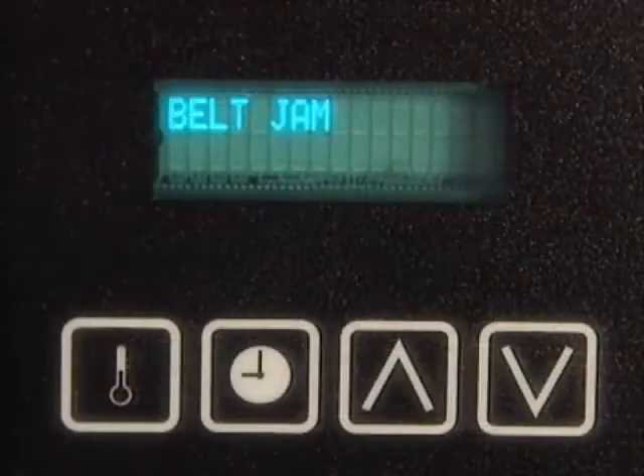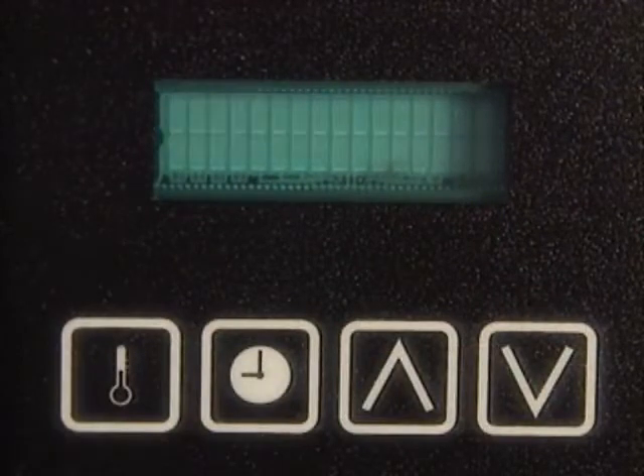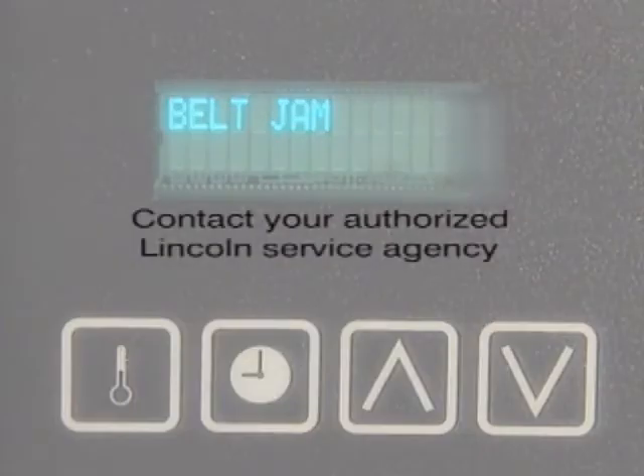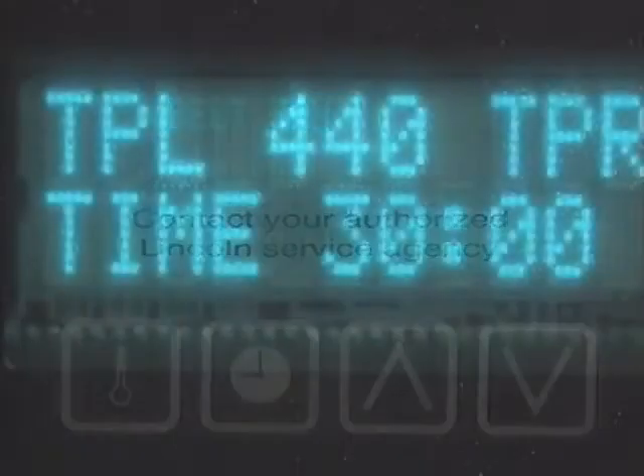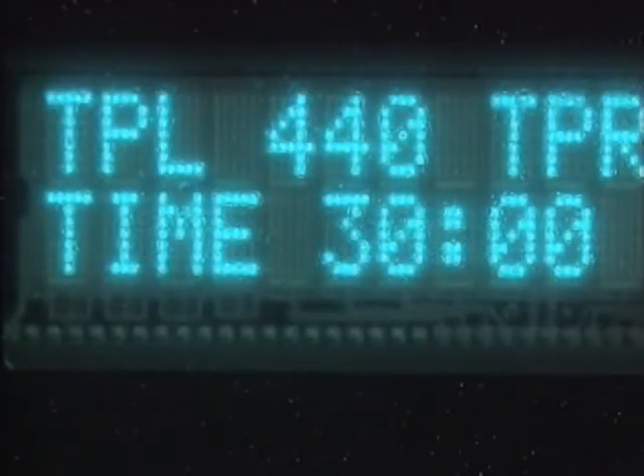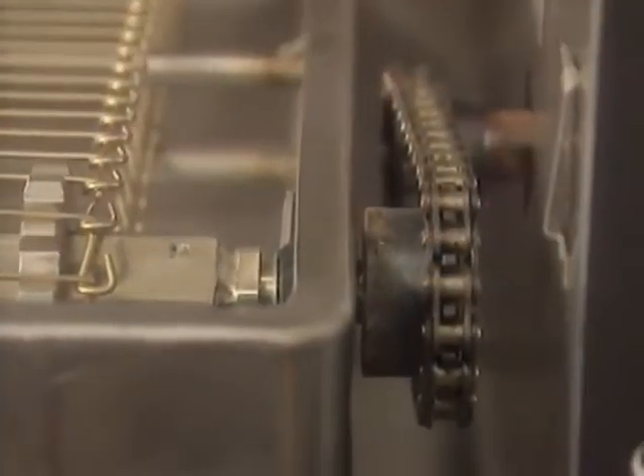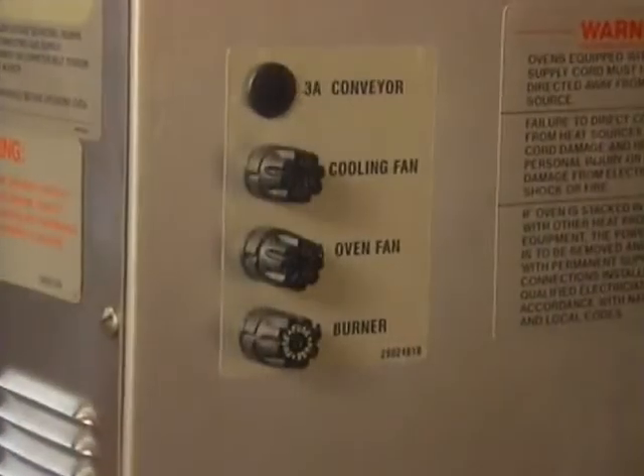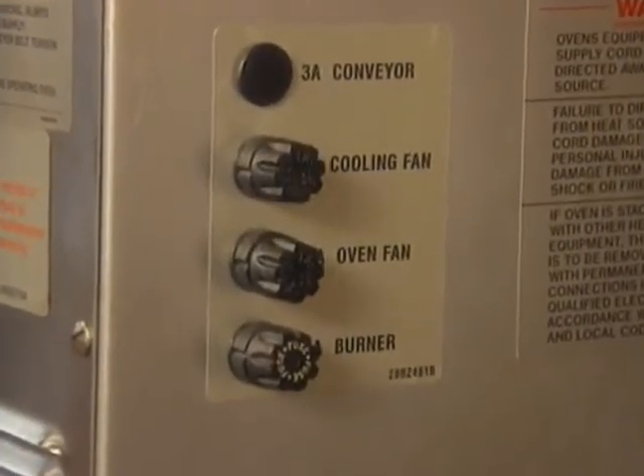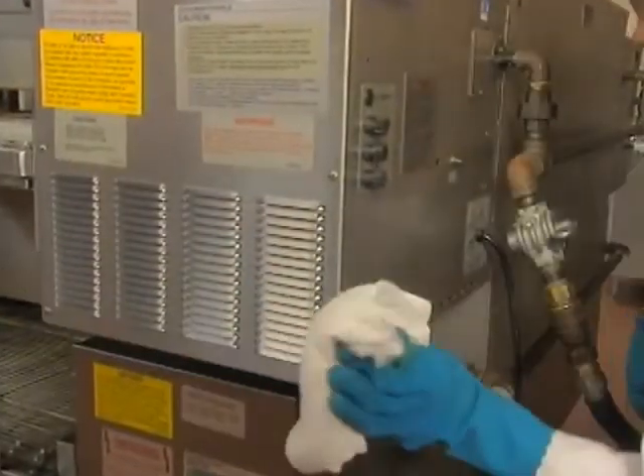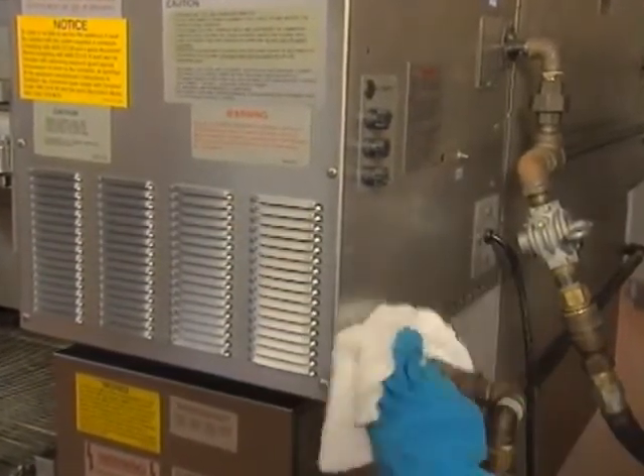If this happens, your display might show the diagnostic message, "Belt Jam." This occurs when the conveyor motor fails, so you'll need to call your Lincoln authorized service agency. If this does not happen, check to see that the belt speed control was not accidentally turned all the way down. Check the drive sprocket chain to ensure they're connected properly. Take corrective action as needed. Next, check your main circuit breakers and fuses. If the conveyor stopped when the oven was hot, it could be overheating. Check and clean the ventilation louvers and cooling fan covers if needed.